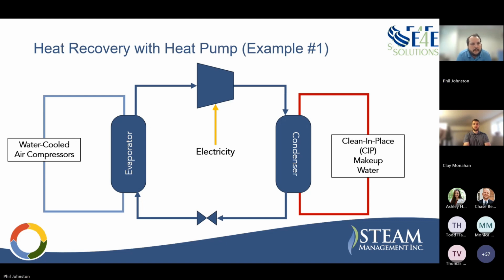But now we have real life applications here with the sources and sinks. So on the source side, we have some water-cooled air compressors. They are currently rejecting this heat to an array of cooling towers. And instead of doing that, we would like to preheat the CIP makeup water that's currently being heated by steam. So let's see how that works.